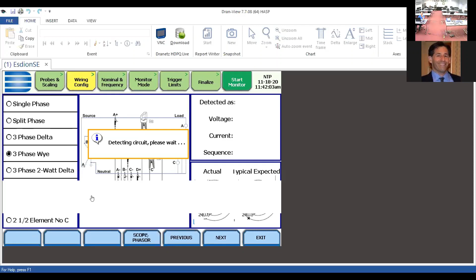There are several pieces of information on this screen that are very useful and beneficial in the monitoring setup. Number one, the instrument will automatically try to sense the circuit type, and it'll come back and say, I think this is a Y circuit, but it might be something different, it might be three-phase delta. This allows you to override that. It might be generic, where, as Ken mentioned at the onset, your typical 8-channel power monitor analyzer can have those 8 channels combined as 4 separate channels for voltage and current monitoring for single phase. There are applications where that would be desirable, and you can override it by selecting the appropriate circuit type for the given application.